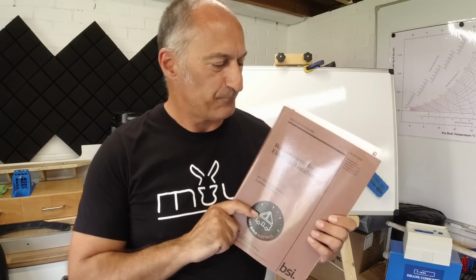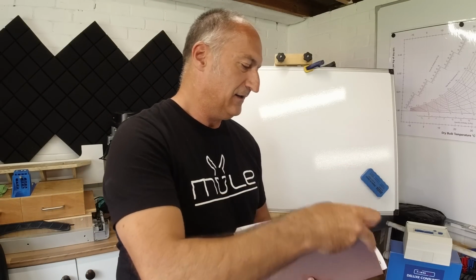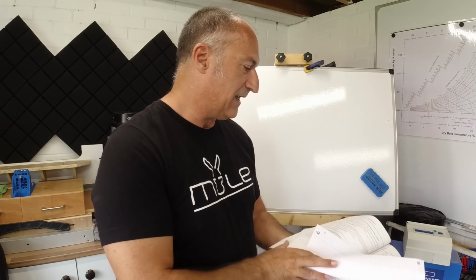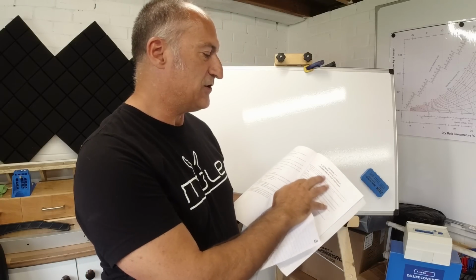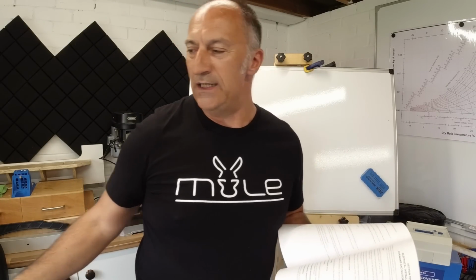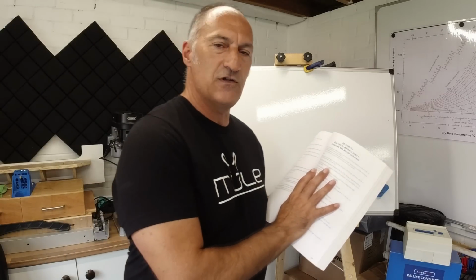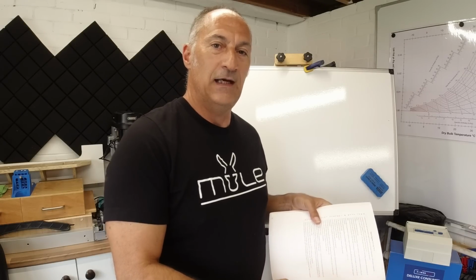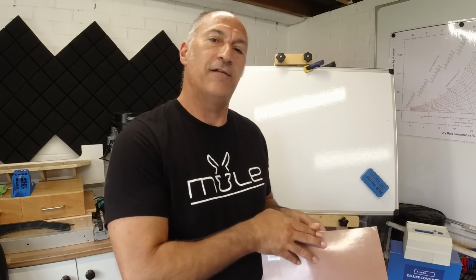Okay, so the current British standards. In section 721 at the back here, there is a regulation that covers electrical installations in caravans and motor caravans, so i.e. camper vans, exactly what we need. And in section 721 there's a couple of paragraphs that state that we do require additional protection in the form of an RCD. It needs to break both the live and neutral, all live conductors. So it needs to be a double pole RCD.